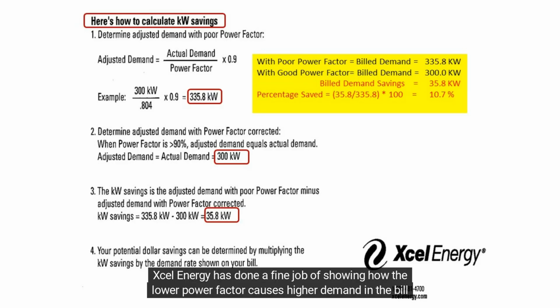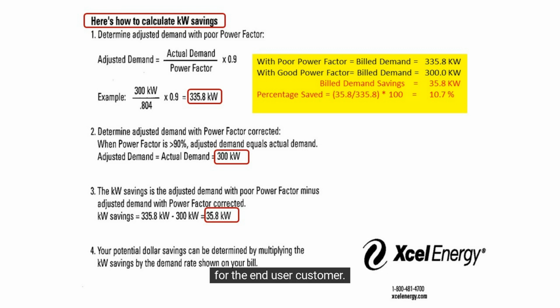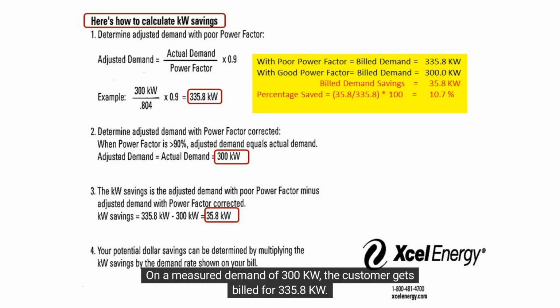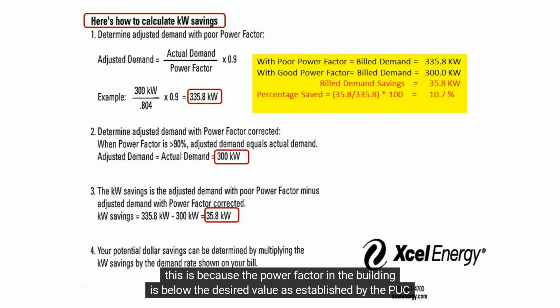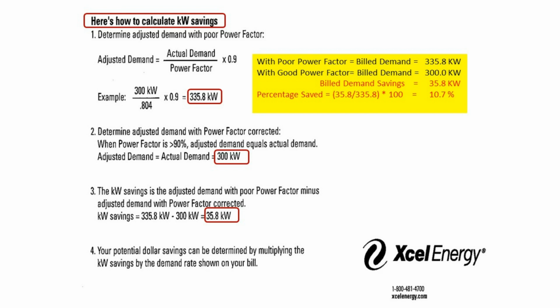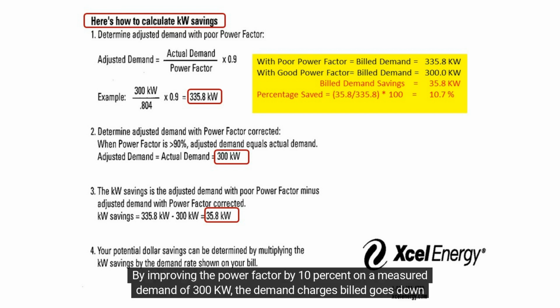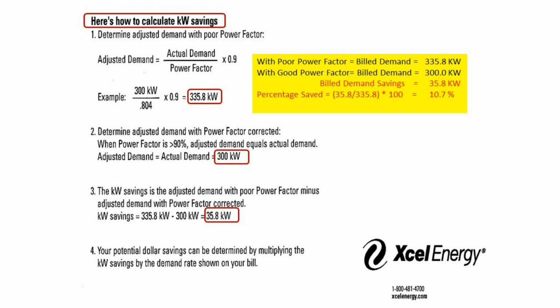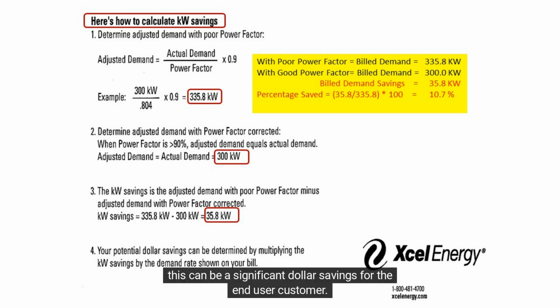Xcel Energy has done a fine job of showing how the lower power factor causes higher demand in the bill for the end user customer. On a measured demand of 300 kW, the customer gets billed for 335.8 kW. This is because the power factor in the building is below the desired value as established by the PUC or end-user tariff agreement. By improving the power factor by 10% on a measured demand of 300 kW, the demand charges bill goes down by 10%. This can be a significant dollar savings for the end-user customer.